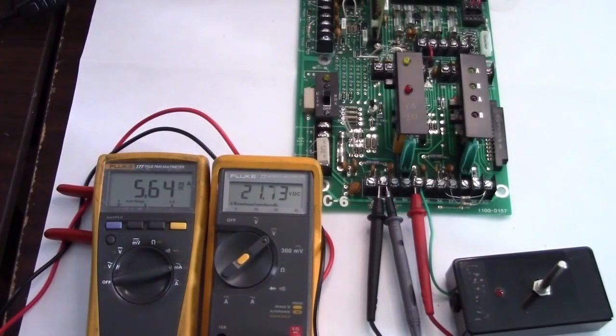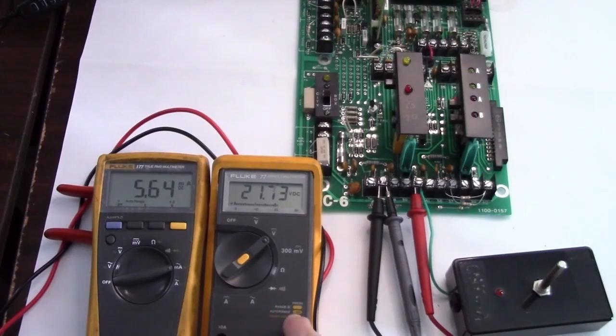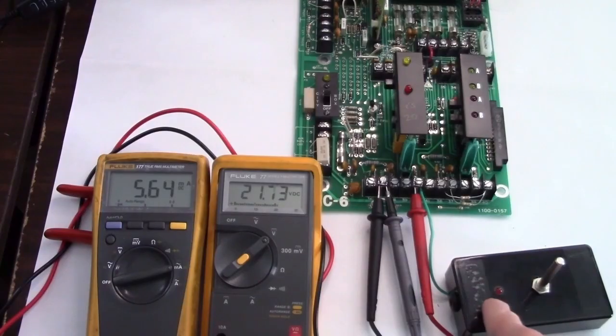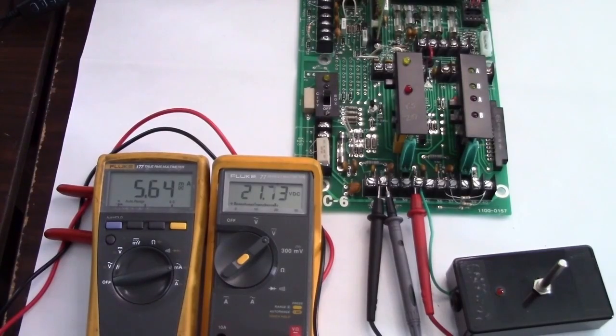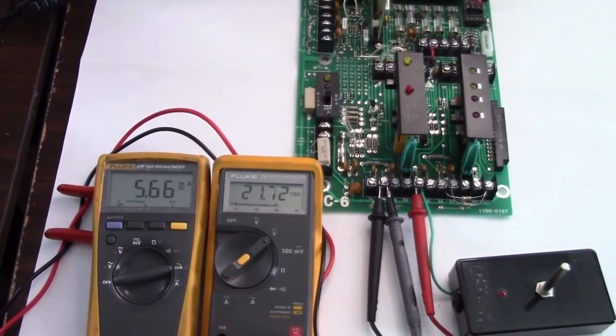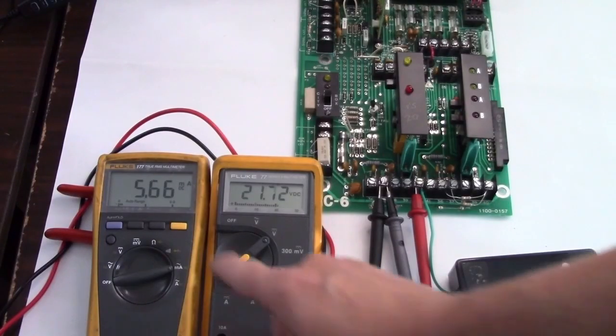To help illustrate how a supervised circuit operates, we have two meters here. The one on the right is set to DC volts and it's connected in parallel across the zone. The one on the left is set to current and is connected in series with its variable resistor. We can determine at what points the zone will go into alarm and trouble. How this operates would also apply to a notification circuit and even a monitor module on an addressable system. Let's watch how the meters are affected as we reduce the resistance across the zone. The current will increase on this meter and the voltage will decrease on this meter per Ohm's law. At some point the zone will go into alarm.